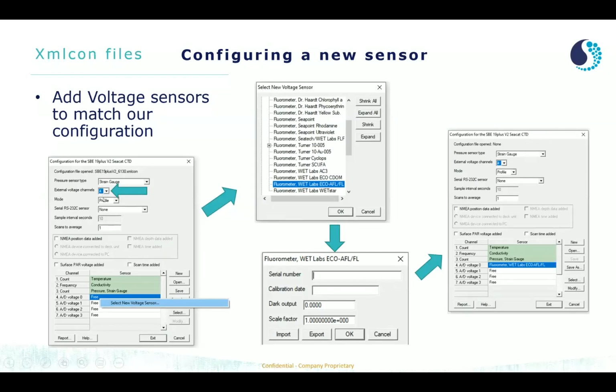In this example, I've got 4 external voltage channels I'd like to fill out, but none of them are filled out yet. So we can right-click the first free section, this is for AD voltage 0, and make sure we select the correct instrument for this voltage sensor from this drop-down. In this case, I've got a fluorometer, and let's make sure we choose the correct one. I can select that, then make sure I put in the correct values for the serial number, calibration date, dark output, and scale factor.